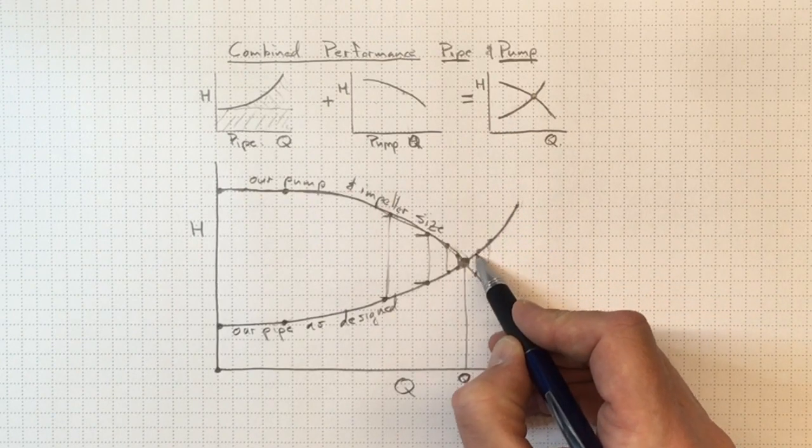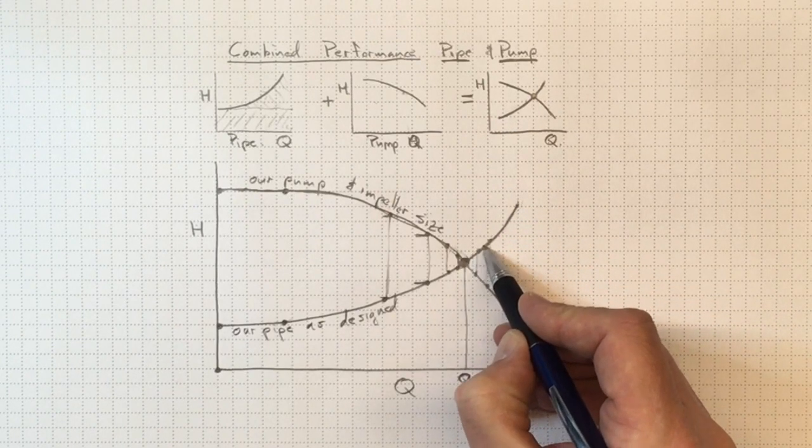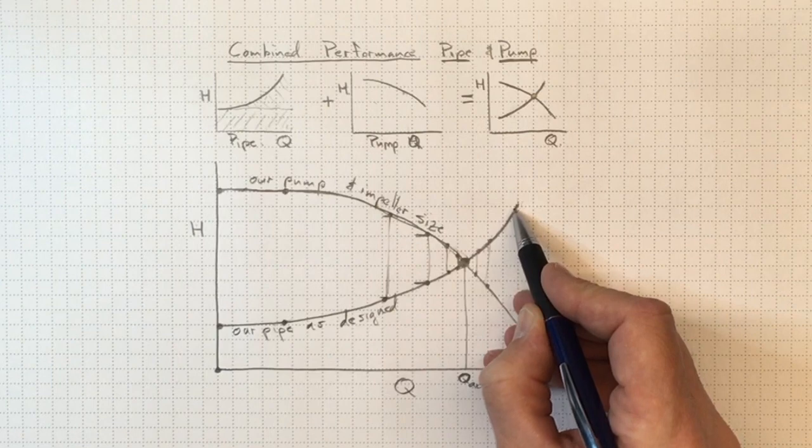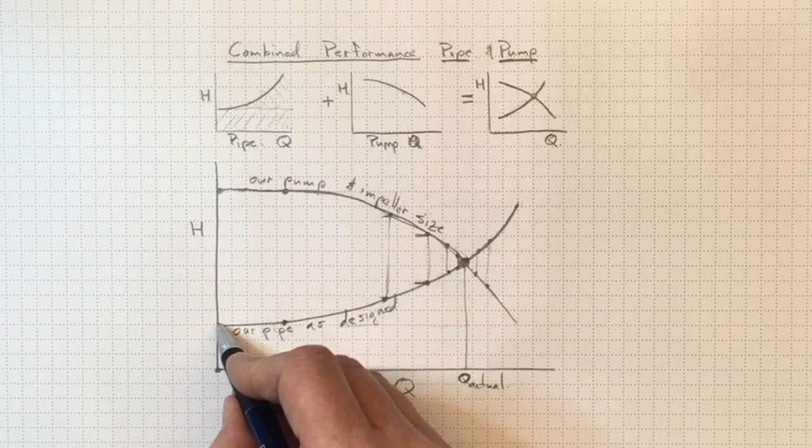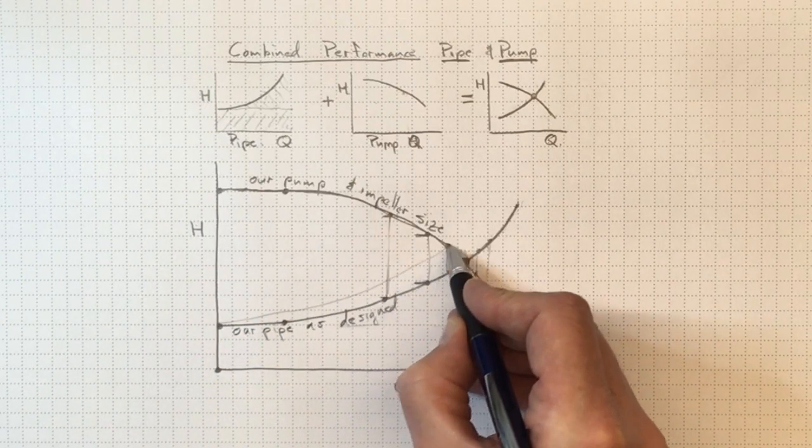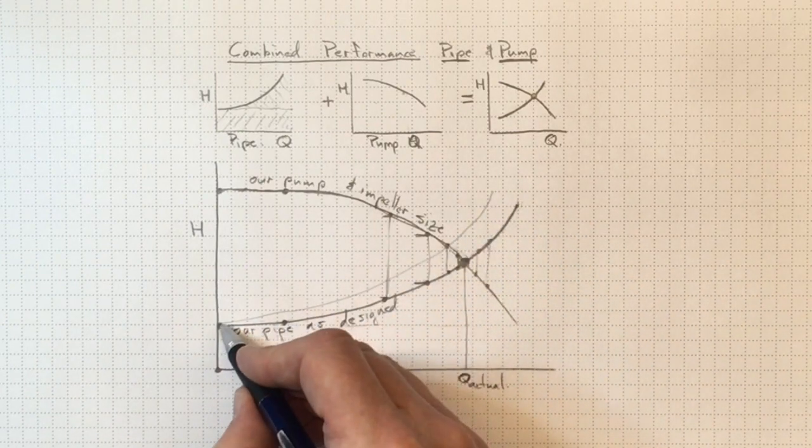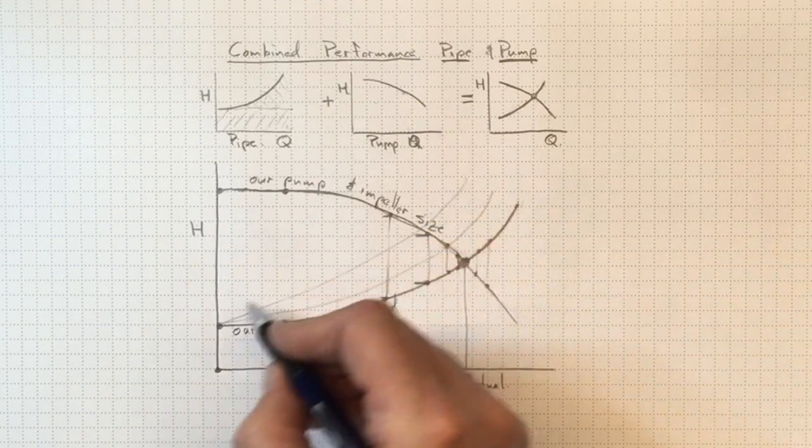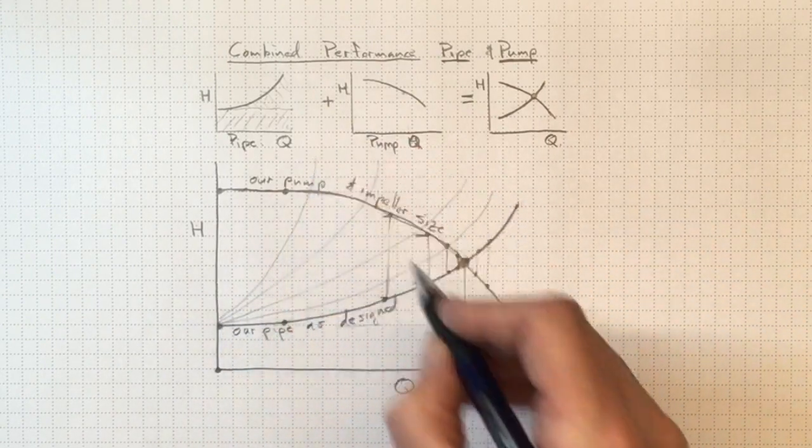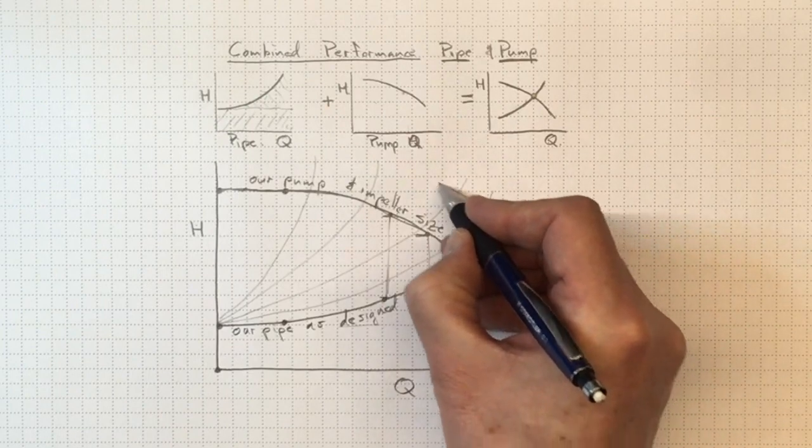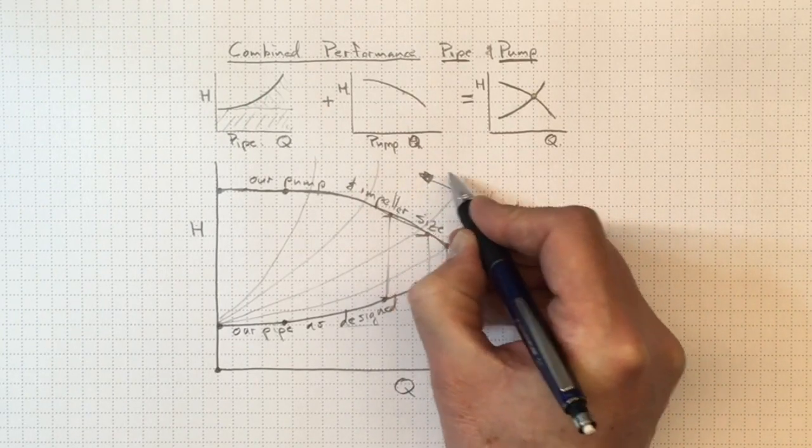But if we've got a piping system that's got a control valve in it, we can always increase the resistance in the piping system. So we'll start with the same elevation difference that we have to overcome, but we might be able to start closing down a valve and get a response curve like that, or like that, or like that, as we keep closing up the valve a little further. So there we are closing a valve.